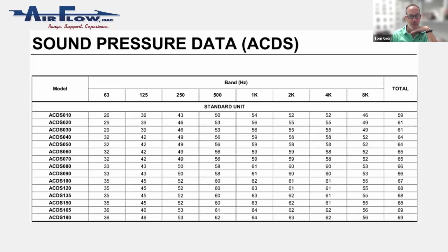If you select a chiller, you're going to get some sound data. First of all, great, it's in all 8 octave bands. This is for a scroll chiller, all the different sizes. For property line issues, we're really dealing with the 250, 500, and 1,000 Hz bands. Notice between a 180 ton chiller and say a 40 ton chiller, there's a 4, 5, 6 dB spread. So dropping the size of the chiller doesn't drop the sound that much. 5 dB is consequential, so know that while I'm working with the biggest chiller here, the smaller chillers aren't necessarily going to be non-problematic. Okay, I've got a good start here.